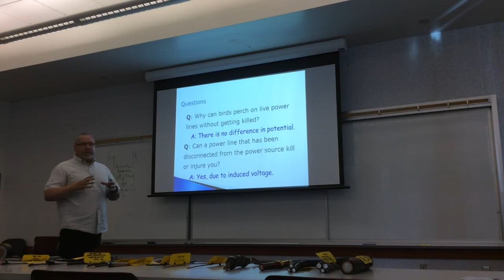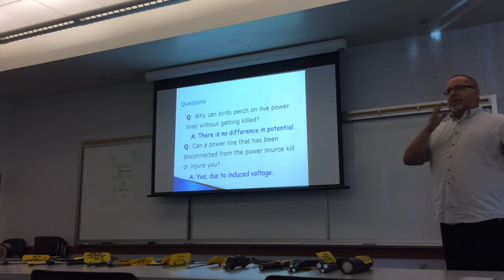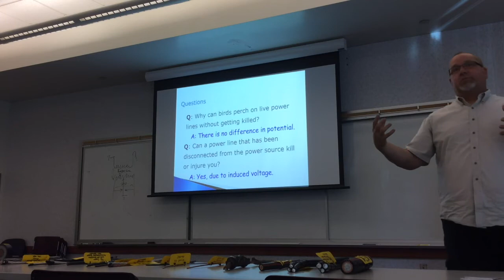Does that make sense? With big power lines, we have to take extra care. When working in corridors with lines like Bonneville's, even though we de-energize and ground our own lines, Bonneville's line running at full capacity can induce enough voltage to make it hazardous to work on our already-grounded line. That's pretty much how the induction system works, but we use it every day in a transformer. Transformers have no physical connection between those coils—it's all induced through an electromagnetic field.